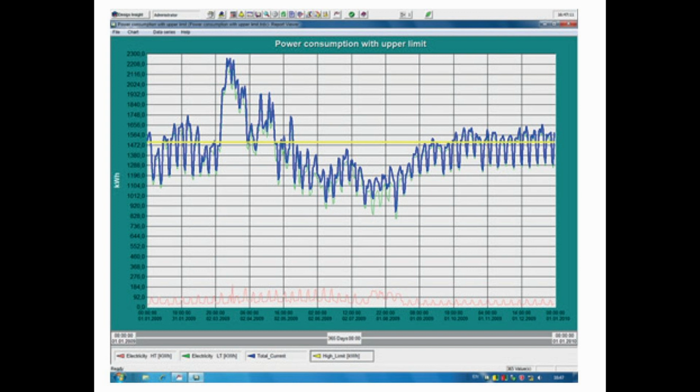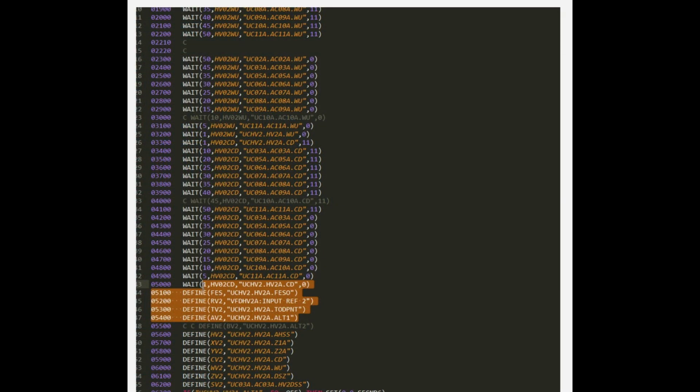The factor that has the greatest influence on program code evaluation speed is the number of FLN devices connected to the field panel running PPCL. The line evaluation rate is also affected by the number of program lines defined in a device.